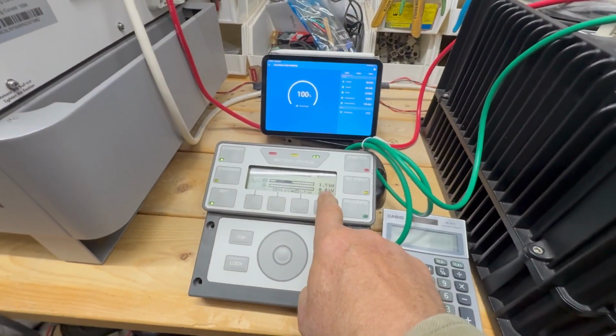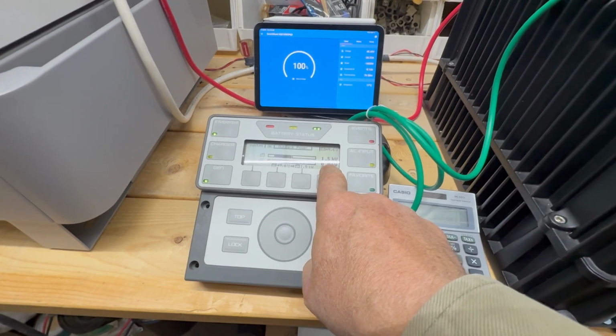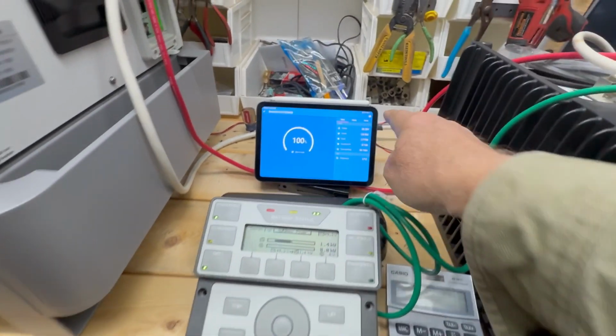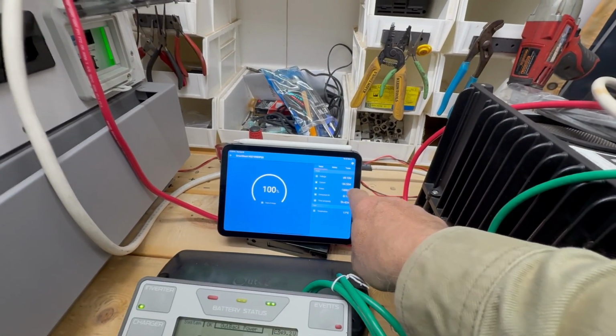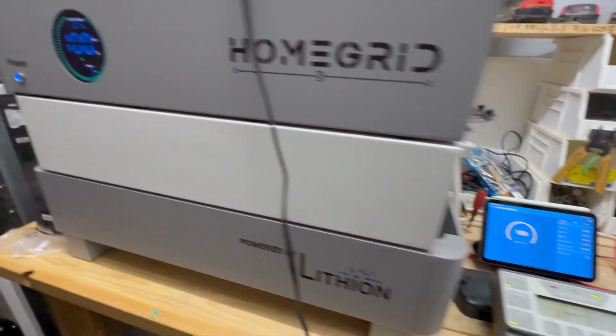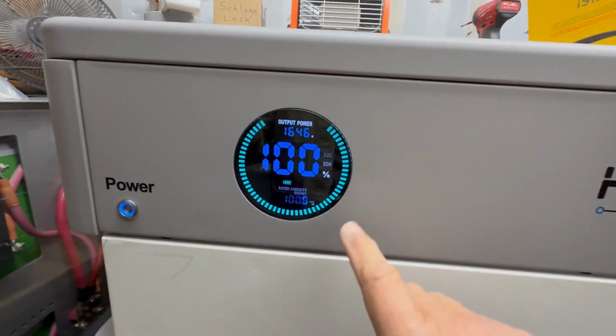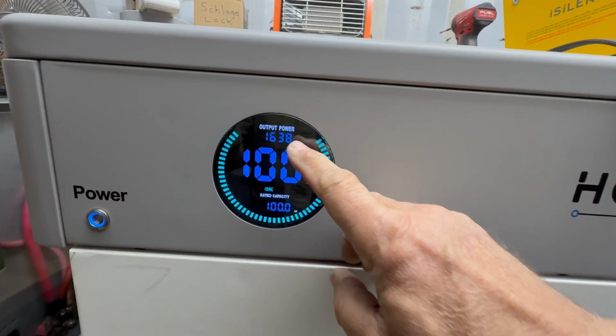Heater. Inverter. Inverter's making 1.5 kilowatts. We're getting 35 amps from the battery. Voltage is still good. Let's run it for a minute. The battery thinks it's actually making 1600 watts.